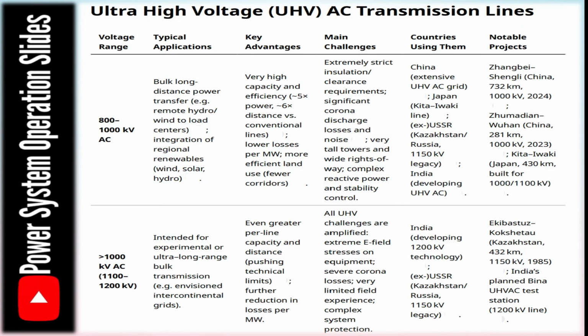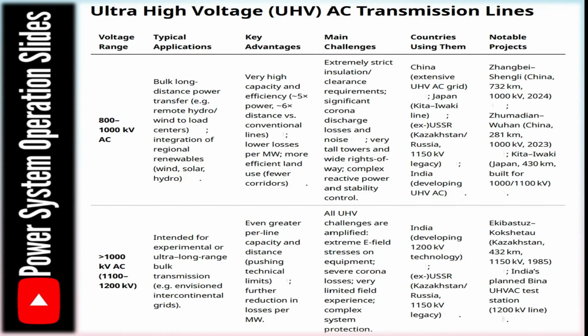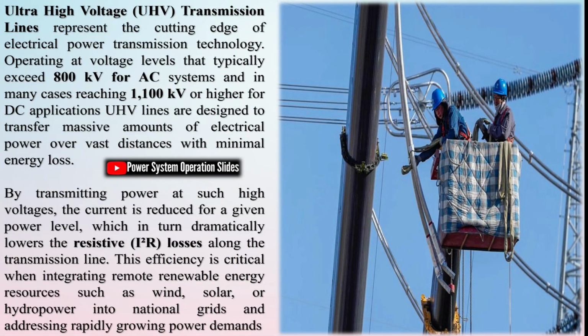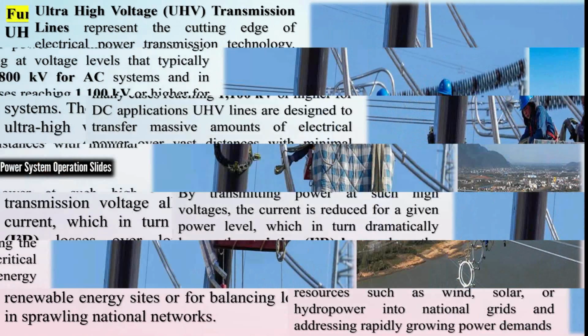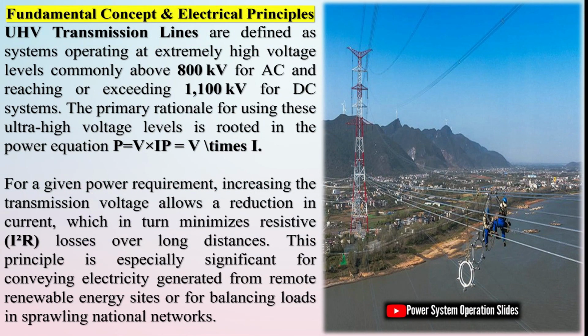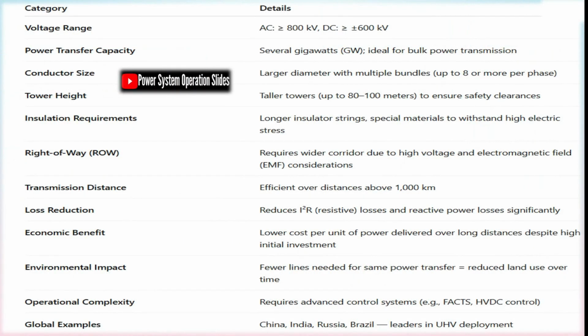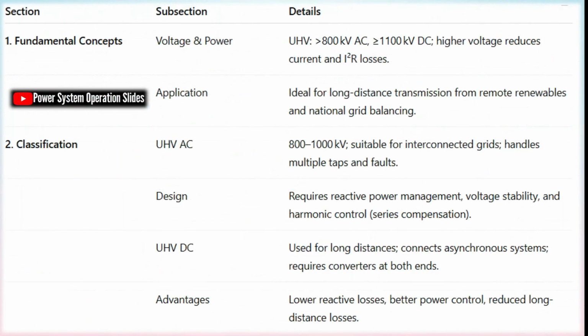UHV transmission lines are defined as systems operating at extremely high voltage levels, commonly above 800 kV for AC and reaching or exceeding 1100 kV for DC systems. The primary rationale for using these ultra-high voltage levels is rooted in the power equation P = V × I. For a given power requirement, increasing the transmission voltage allows a reduction in current, which in turn minimizes resistive I²R losses over long distances. This principle is especially significant for conveying electricity generated from remote renewable energy sites or for balancing loads in sprawling national networks.